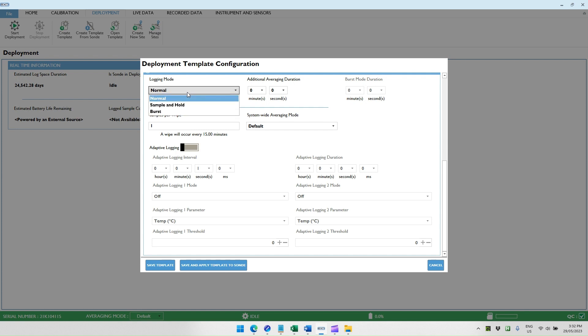To fix that, we use the sample and hold logging mode. The sample and hold logging mode means that when the sonde takes a measurement according to its internal schedule, it records the data and holds that data available to the AI-1 for when the AI-1 requests a measurement. If the sonde is measuring every 15 minutes and then the AI-1 comes along and requests a measurement, it will provide the most recent measurement to the AI-1. This means it is not causing a conflict between the sonde wanting to do a measurement and the AI-1 wanting to do a wipe because the AI-1 just receives a previously held value. We highly recommend that you use sample and hold.